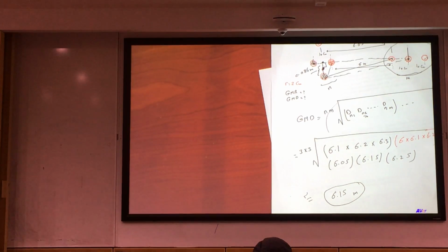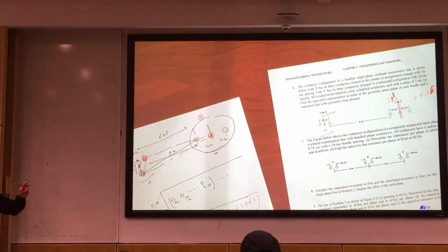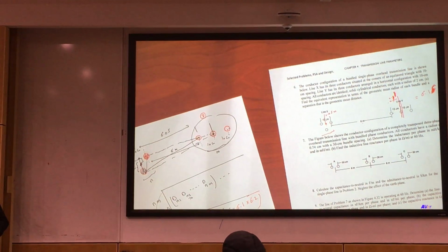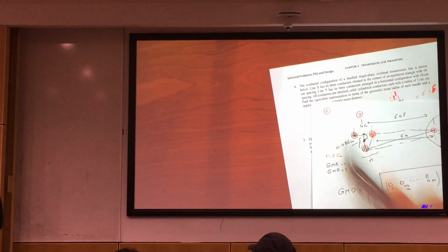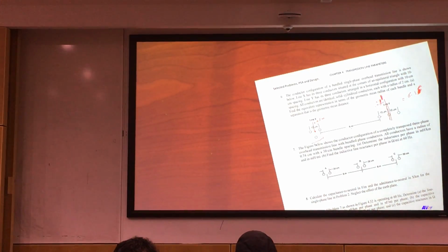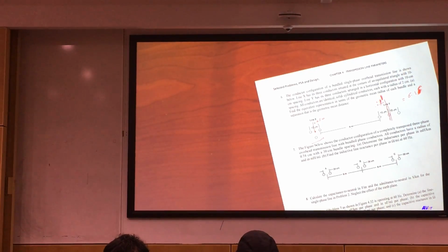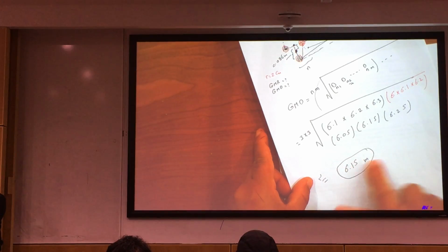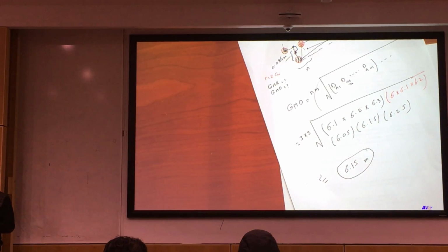So in some discrete configurations like this configuration here, when we don't have any symmetry between x side and y side, we try to estimate the center of each side and calculate the distance between this center and this center. Otherwise, we have to follow it in this way. But you will get almost a slight difference between the actual geometrical mean distance calculated from here and the one calculated from this center to this center. So if you do that, you get the geometrical mean distance like this, and this value is again the same for C and L calculation.